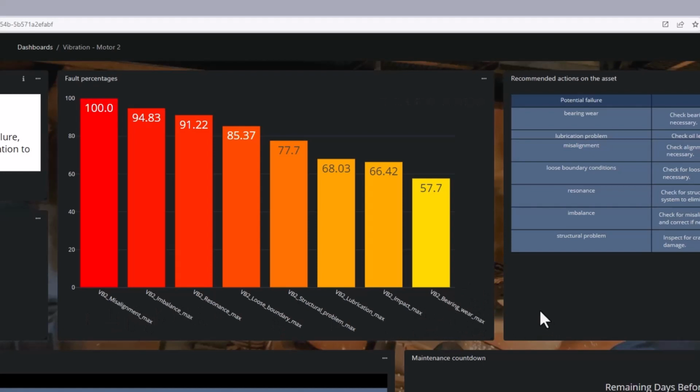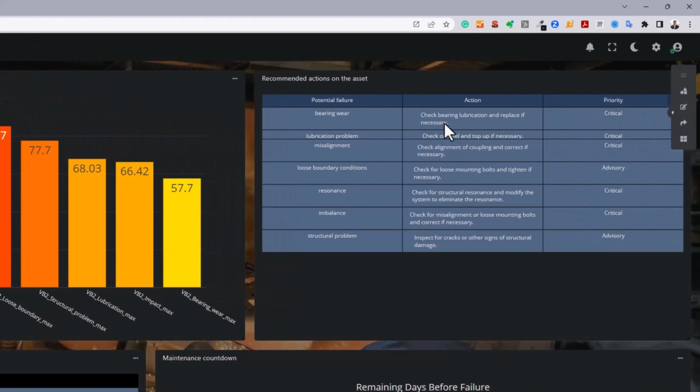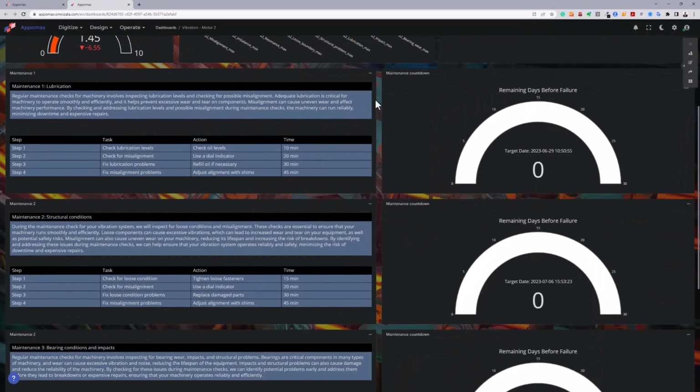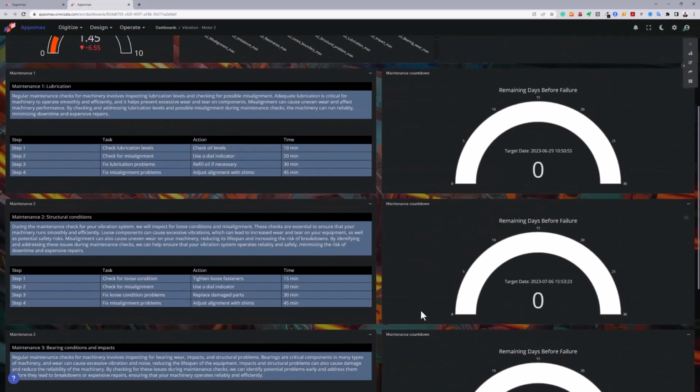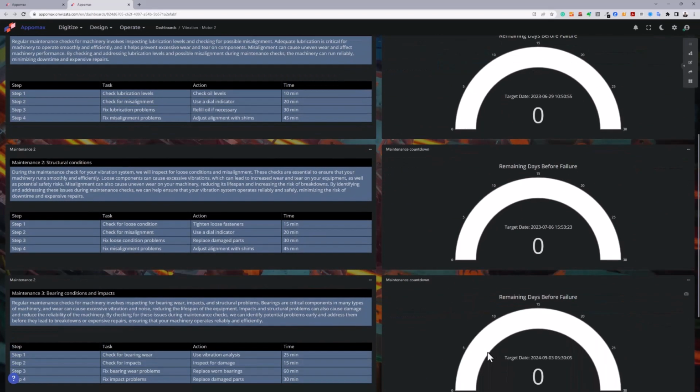I suppose you can tell from what frequency the vibration is at, and other factors based on the parameters read from the vibration. And here are some recommendations along with the remaining days before failure. What it's saying is like 0 days. These are some forecasts of days to unacceptable level.